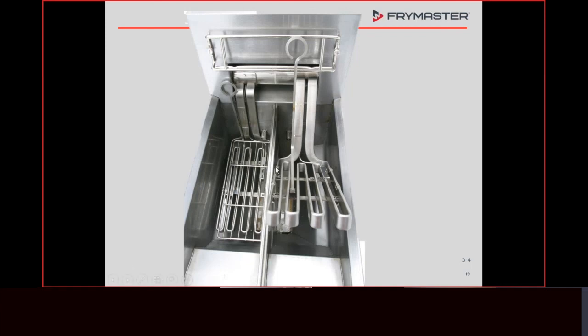But again, swelling, discoloration, if this line in the back all changes, those are signs that we got issues with those elements. That one where you see the bubbles coming up, it needs to be changed. That's just not something that may happen, it's going to happen. That insulation has been compromised inside the cladding here.